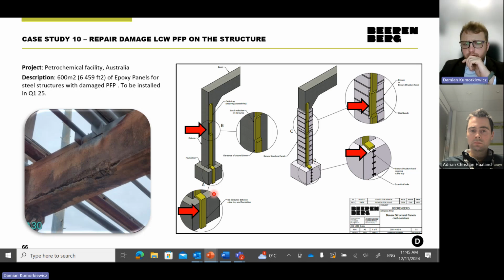Also here you have no clearance between the cable trays and the foundation, so we fireproofed the entire foundation, as you can see here, while the cable tray penetrates through the panels. These minor gaps will be sealed by intumescent tape, which was shown at the beginning of this presentation. So this is how we're going to do it.